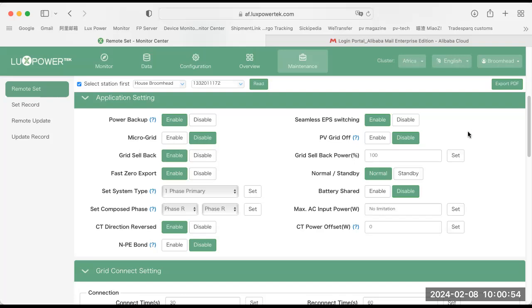All right, PV off-grid. This you will enable if you're running a site where it's an off-grid site, or a site that's got no batteries, but it's got PV. So by enabling this here, this will allow you to output power in the case of solar, but no battery. Just remember that the reactive power on solar is a lot slower than what it is on battery. So always make sure that your sizing of your PV is much bigger than what your loads are. All right, grid sellback. You guys are very familiar with this. This is where you can sell power back to utility, and here you will set the power rating.